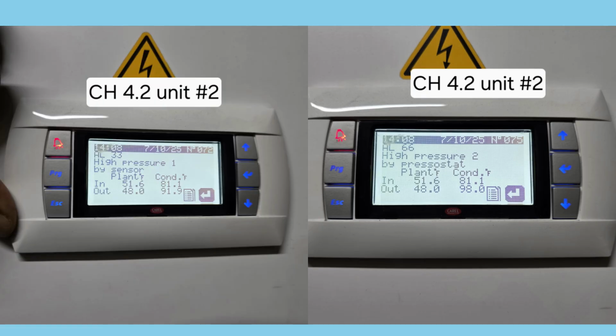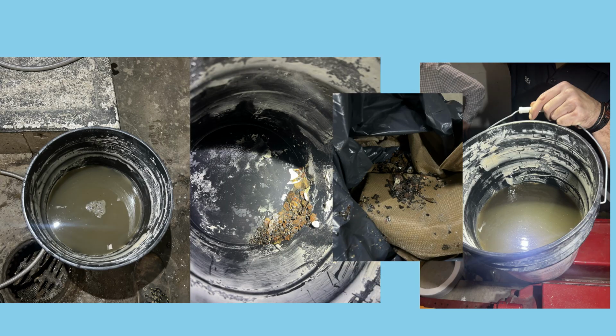In this picture, you can see that unit went on high pressure alarm. The condenser water loop temperature is not bad as well, so what might trigger the high pressure alarm? These photos clearly show contaminated and heavily corroded condenser water, with visible rust flakes, scale, sludge, and dirty water, and that directly explains why the heat pump is tripping on high-pressure alarm. In a water-to-water or air-to-water heat pump, the condenser water loop, hot side, is supposed to carry heat away from the refrigerant. When the water is dirty, rusty, or contains debris, several things happen.